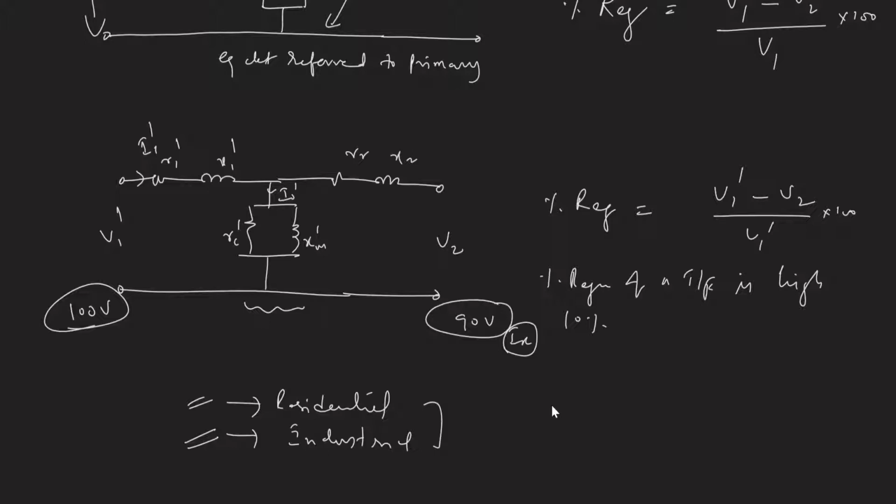So we have to make sure that the voltage deviation at the terminals of my transformer should not vary by a very large quantity. Okay, it should vary only 1% to 2%, or in the case of power transformers, it's okay if it goes a bit higher, more than 3%.